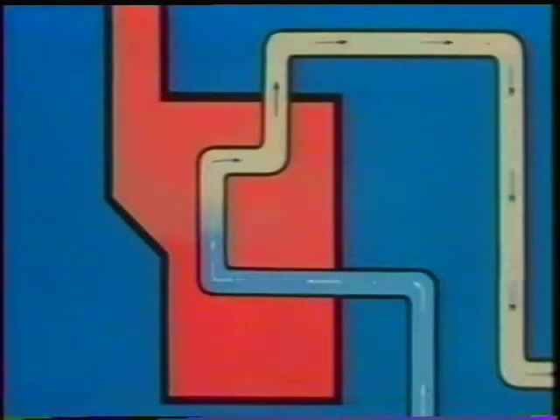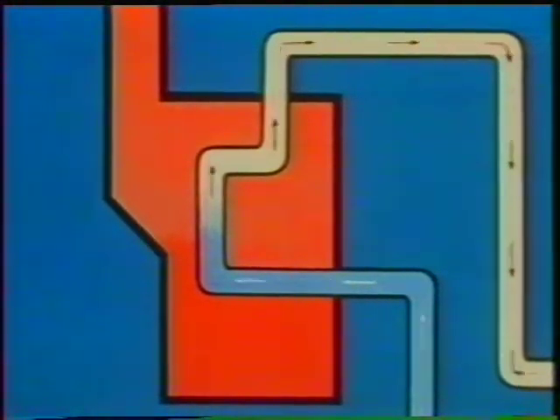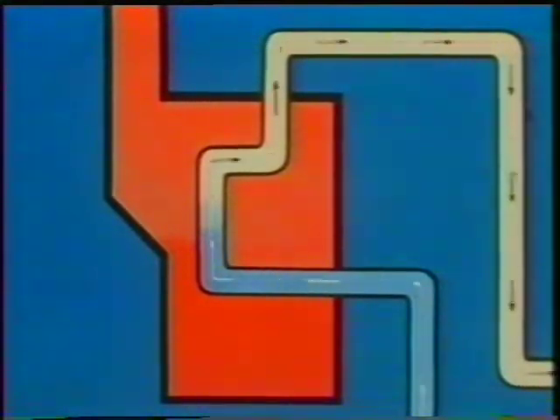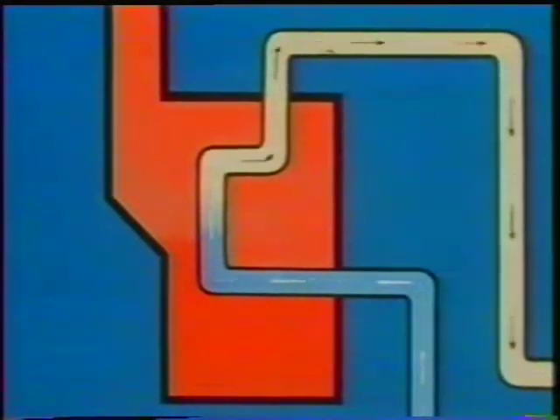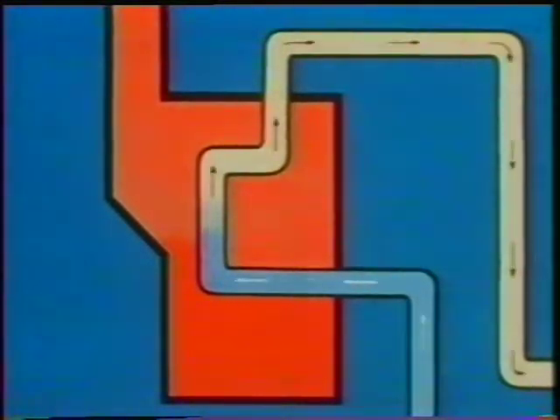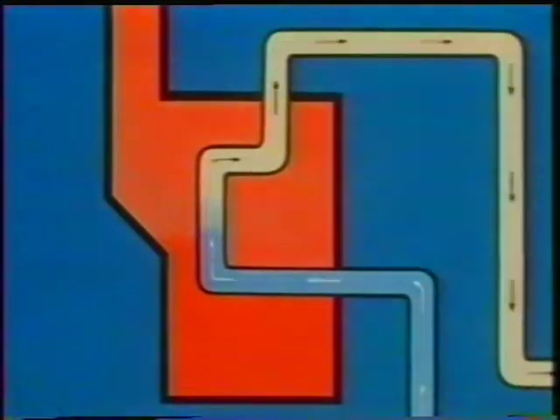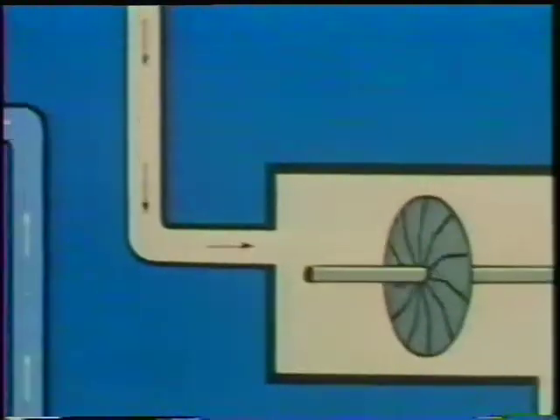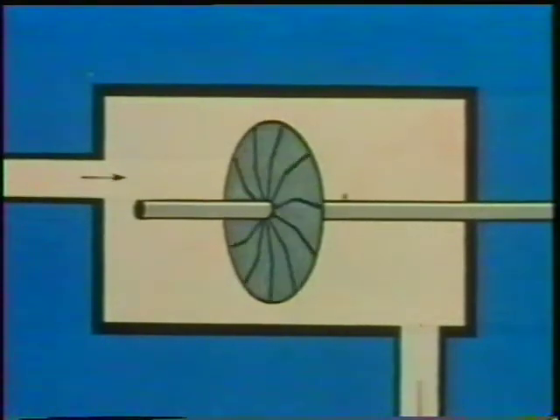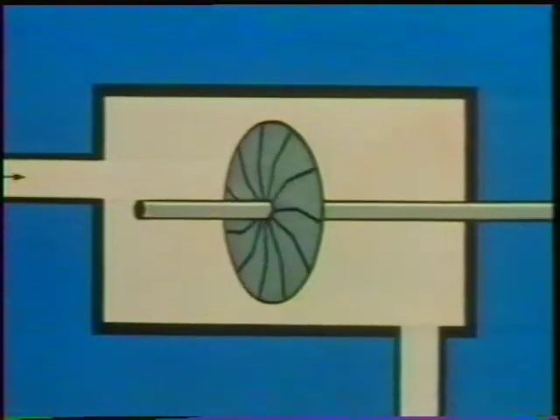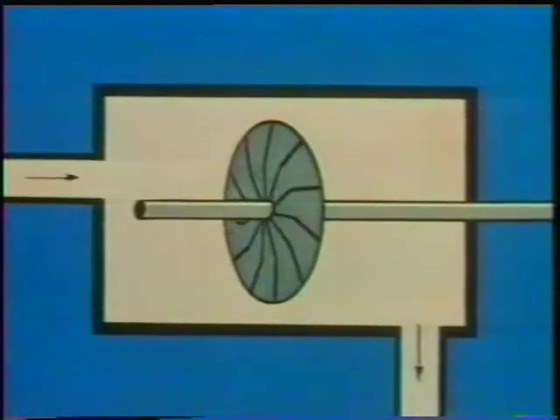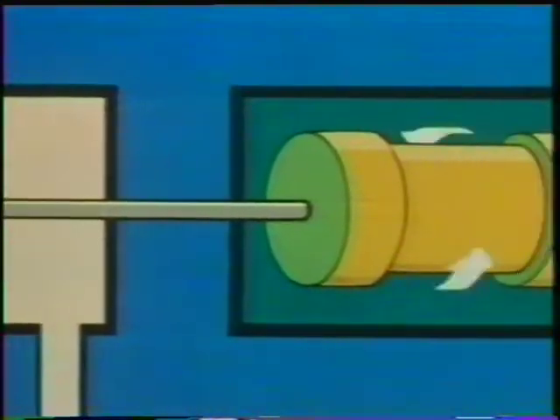Here's a simplified diagram. The furnace is like a giant hollow box with pipes running up inside it. The heat from the burning coal boils water in the pipes, the boiler tubes, turning it into steam, which passes out through the pipes at the top. This steam, superheated to a very high temperature, passes along pipes to turbines. Here, mechanical energy is produced as the steam makes the turbine blades rotate. This mechanical energy of rotation is turned into electrical energy by the generators.